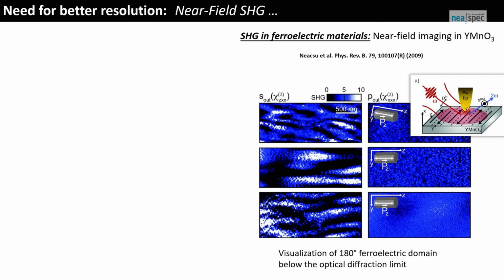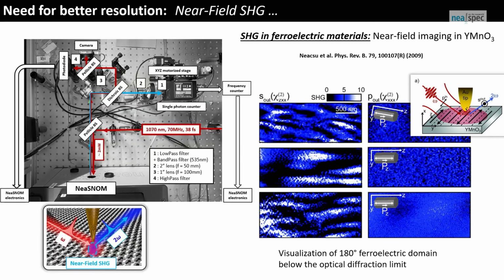So this is where we got into this world, and then we acquired a neaSNOM microscope. But the thing is, in this case, the amount of photons you will collect with second harmonic generation, if we are lucky, is going to be in the range of 10,000 to hundreds of thousands of counts per second. So we could not use a standard photodiode, so we had to have this single photon counter that we bought from Hamamatsu. And so this is basically the path.